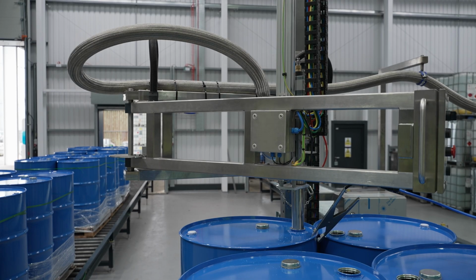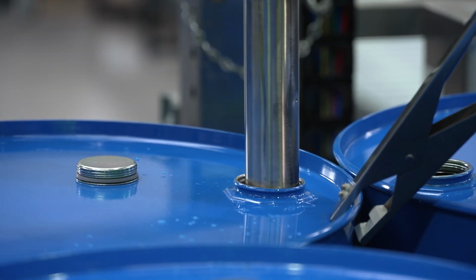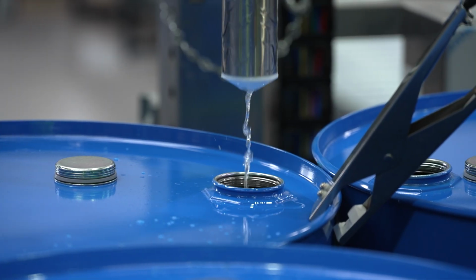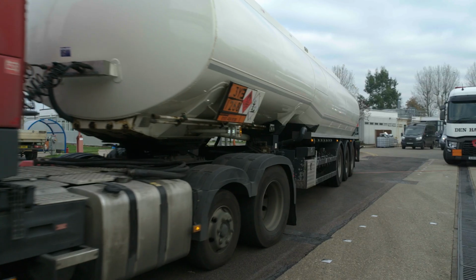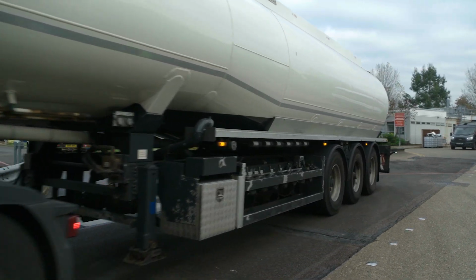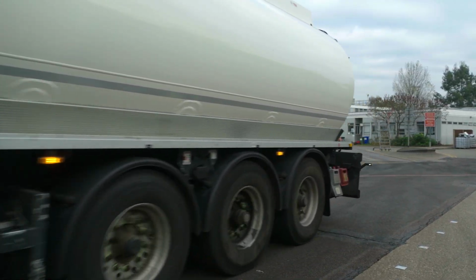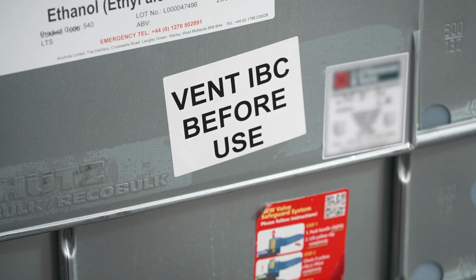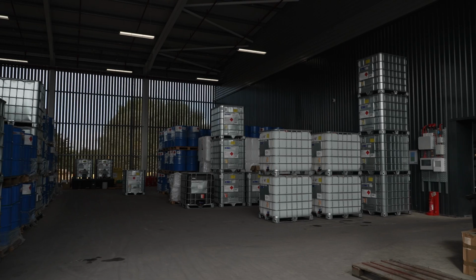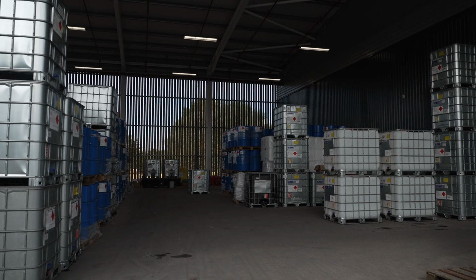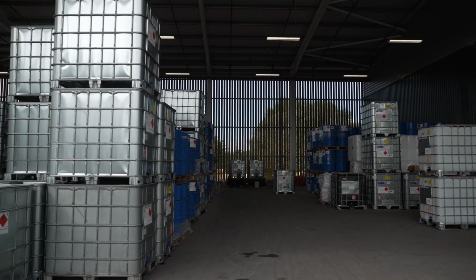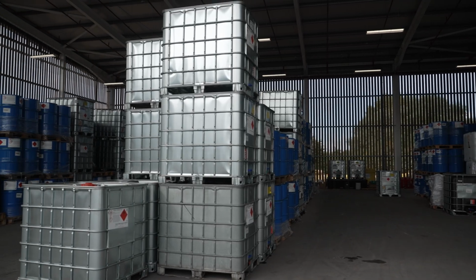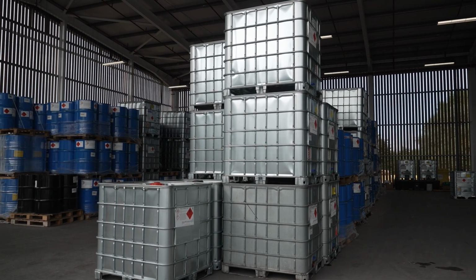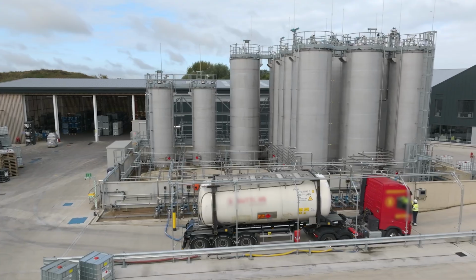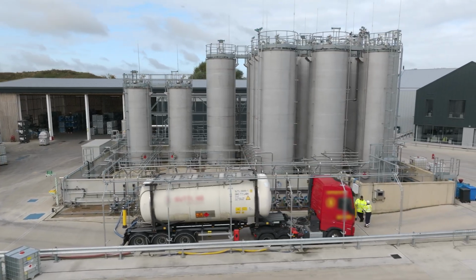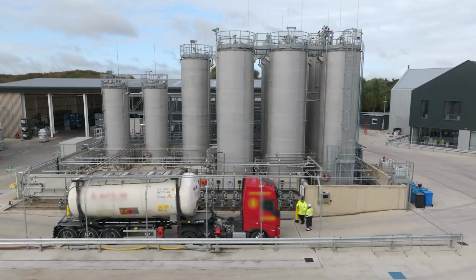It is particularly important that the velocity of the liquid being transferred is controlled, so operations such as gravity filling of IBCs from road vehicles should be avoided. After completing a filling operation, it may be necessary to sample the liquid. A sufficient relaxation time should be allowed for the accumulated electrostatic charge to dissipate. Care must be taken when the receiving tank or container has not been cleaned out and contains flammable vapor.